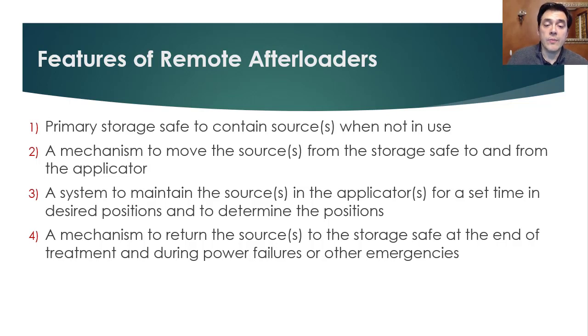Number two, a mechanism to move the source from the storage safe to and from the applicator. Number three, a system to maintain the sources in the applicators for a set time and desired positions to determine those positions. Number four, a mechanism to return the source to the storage safe at the end of the treatment and during power failures or other emergencies.